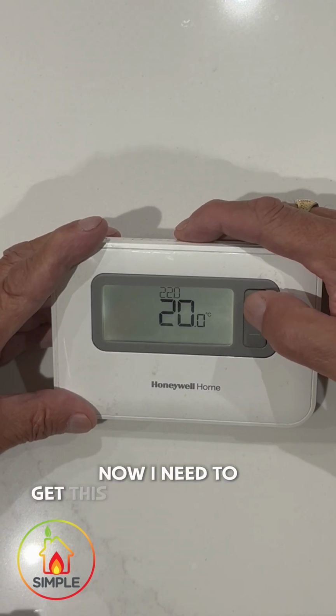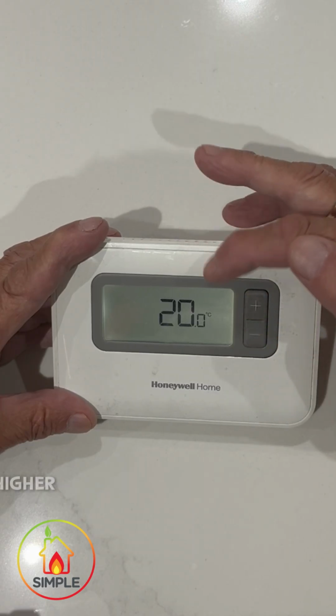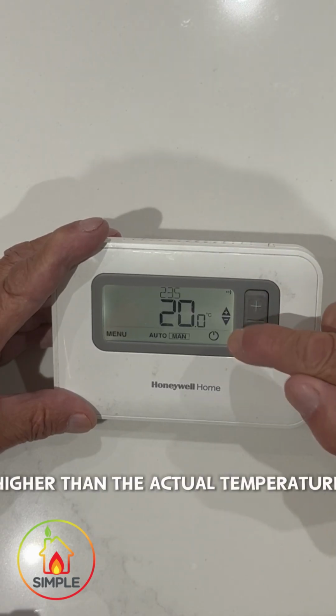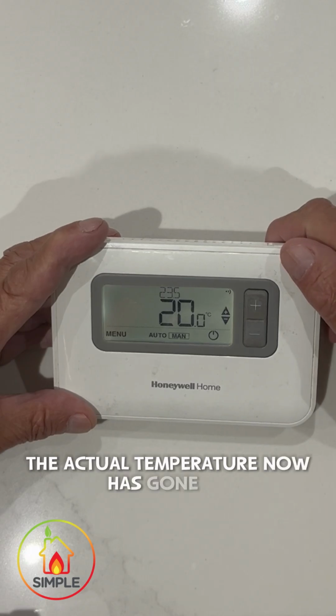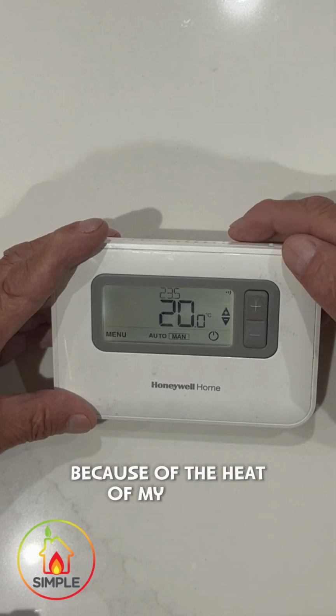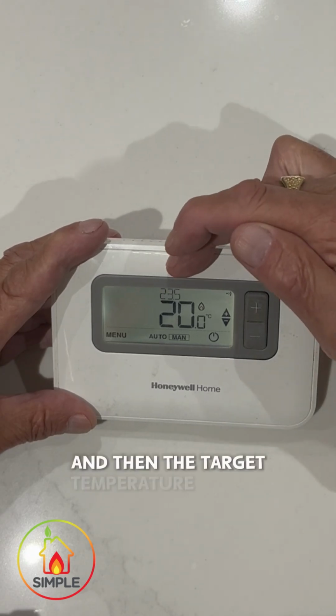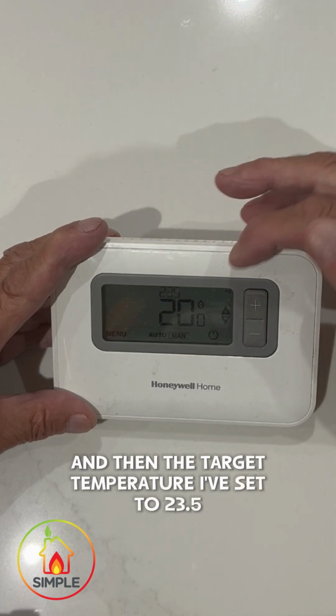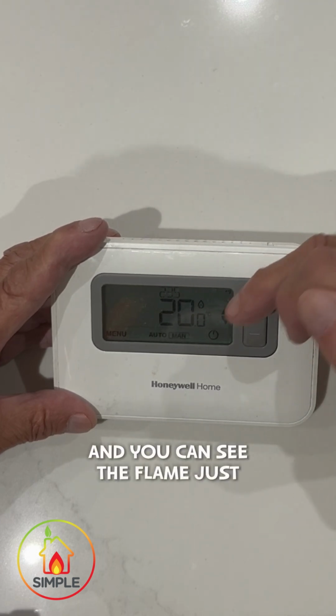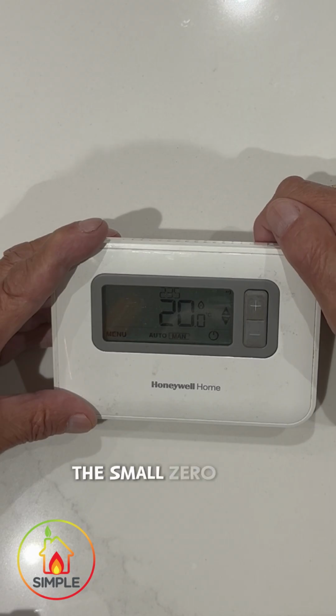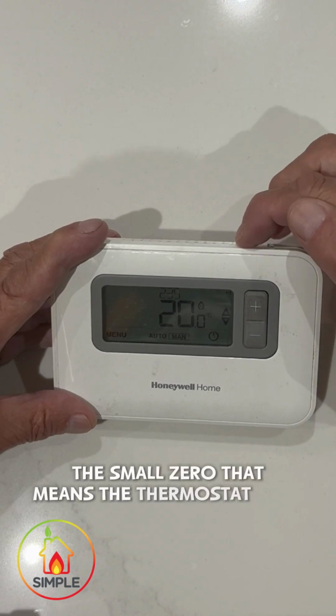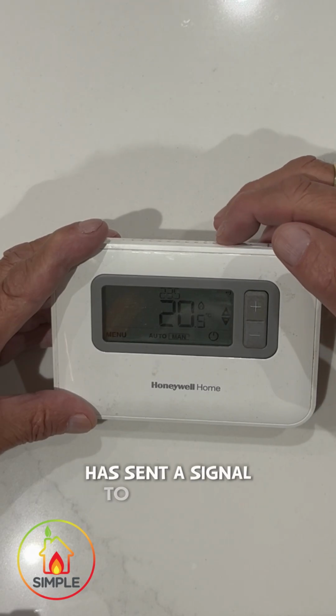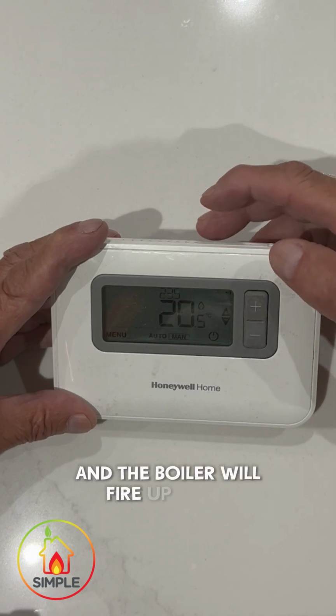Now I need to get this target temperature higher than the actual temperature. The actual temperature has gone up to 20 degrees because of the heat off my hands, and the target temperature I've set to 22.5. You can see the flame just come on above the small zero. That means the thermostat has sent a signal to the boiler, and the boiler will fire up.